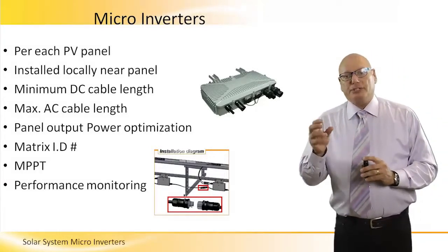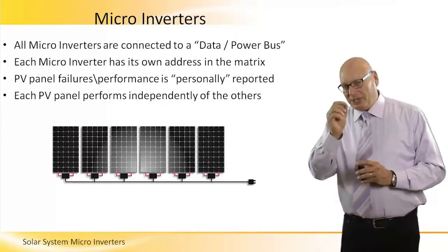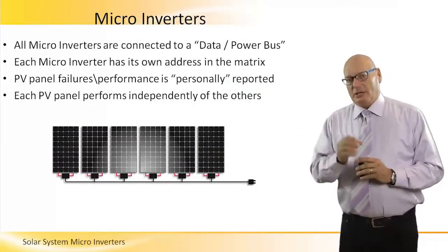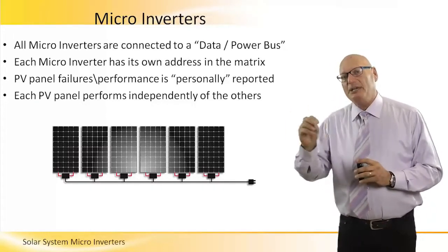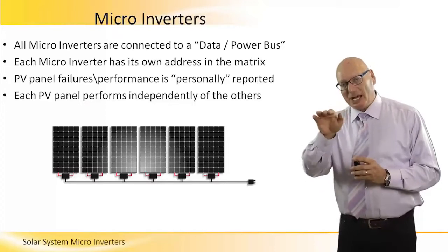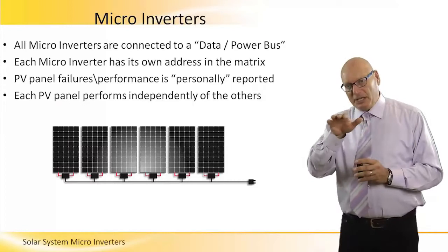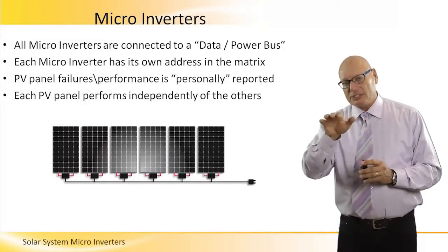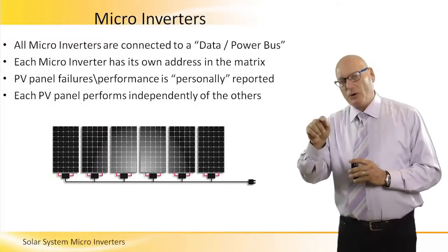All microinverters are connected to a data and power bus. The data and power bus uses a technology called PLC, power line carrier, meaning the data coming out of the microinverter is transported on the cables. Data on copper.